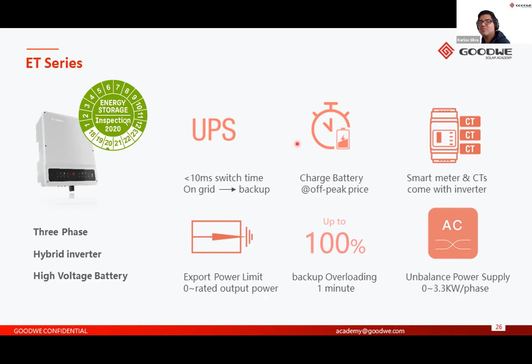Here's a 6 ET inverter system connected to a SEC 1000S, around 60 to 80 kilowatts of PV power, with 6 separate battery banks, each connected to its own ET inverter. The SEC 1000S brings a lot of flexibility, including being able to connect different batteries at different capacities to each inverter. As you can see here, this battery has 7 modules, whereas this one has 6 battery modules, so you can connect batteries with different capacities to one inverter.